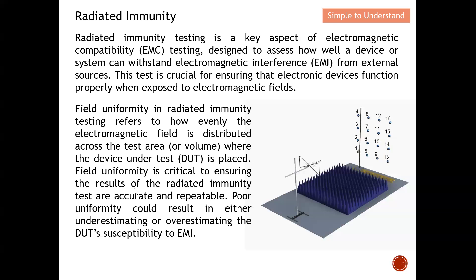Field uniformity is critical to ensure that the results of radiated immunity tests are accurate and repeatable. Poor uniformity could result in either underestimating or overestimating the DUT's performance. For example, if one point has a much lower field than another, the result depends on the DUT's orientation — it may pass the test in one position but fail in another. Field uniformity ensures that all 16 points have approximately the same volt-per-meter value, so the field is evenly distributed.